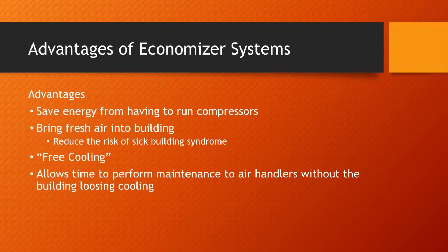Another big advantage is you're bringing that fresh air in. So if you're in a region where it's kind of mild and you're sometimes worried about that minimum fresh air requirement, once you go into economizer mode, you don't need to worry about that. You're running on basically 100% outside air. You are going to get those air changes per hour, no problem at all.